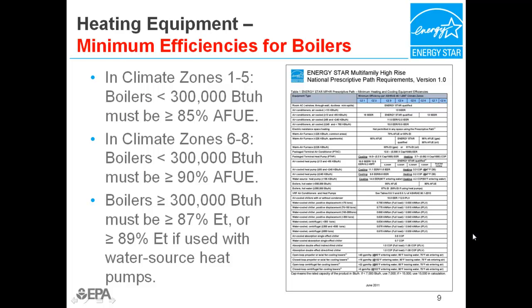Although not all equipment in Table 1 will be reviewed in this webinar, the most common systems will be hot water boilers, gas or oil fired, that are less than 300,000 BTUs per hour must be 85% AFUE or better. If located in the colder climate zones of 6, 7, or 8, they must be 90% AFUE or better. Larger hot water boilers, gas or oil fired, that are greater than 300,000 BTUs per hour must be 87% efficient or better. If used with water source heat pumps, these boilers must be 89% efficient or better.